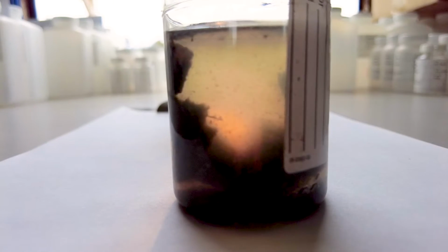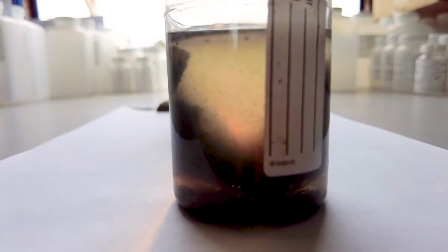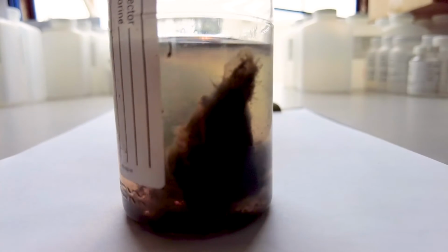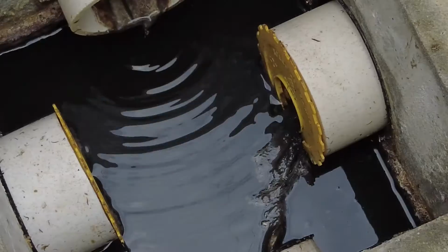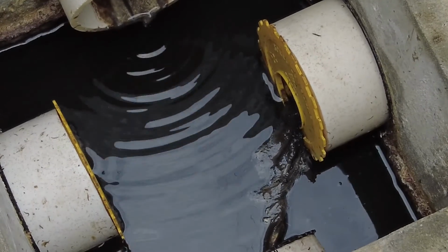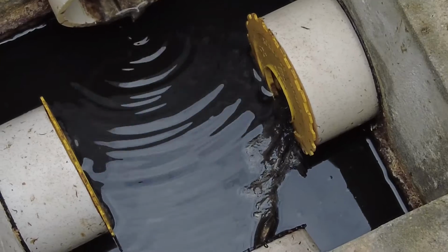And so, a clean or a dirty sample has maybe some dirt in it that's going to affect your results? Well, it may have dirt, it might have the sludge that settles out and is not representative of what's going out to the system. Because in any system, if you slow the flow down, like in a distribution box before it goes out to the leach field, then there's going to be some material that settles over time. And what's in the bottom of that D-box isn't going out to the system each time. It's settled. But if you disturb it, now you're getting the results of settling over months of time.